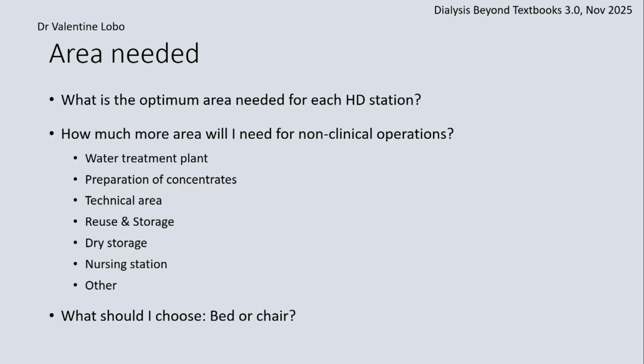Chemical storage and where your water treatment system is. If you're going to use resins and you're going to use acid and alkali for regeneration, spillage of acid and alkali will make a mess of your floor. Yes. It always corrodes, and corrodes structurally. So it is better, if you can, today, you should have an electric DI that takes away the acid and alkali spill. Yes. But if you have it, then it must have a separate clear-cut drainage, and the floor needs to be done with FRP-proof tiles, so that there are no leaks between. So you need to do waterproofing with the same material. Otherwise, you are definitely going to destroy the floor. Yes.